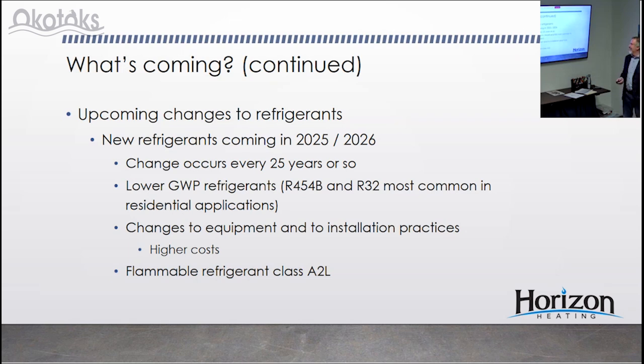Just wondering about the refrigerant. Does somebody professionally have to come in and check that? We could, but I wouldn't recommend tapping into the system. We would be checking temperatures. You can check the operation of the refrigerant from the temperature that it's running at. Every time you put a gauge on a system, you're actually removing a tiny bit of refrigerant, so over time you're going to need a top up. Now, if you find that your system's not working and it's not cooling properly or it's freezing up or something, then we should put some gauges on and see what's going on. But typically, we're checking temperature.